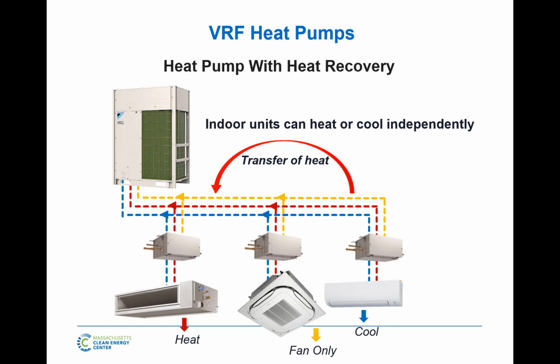I don't think I've seen yet in my career somebody decide to go from a heat pump system to a heat recovery system for the sole purpose of the energy efficiency of the heat transfer. The decision is usually on, does my building need independent, simultaneous heating and cooling in all my units or not? A school might say, yeah, okay, put 4 classrooms that face north on one system, and that's fine. I don't have to heat one while I cool the other.